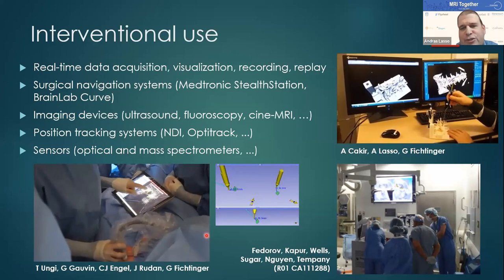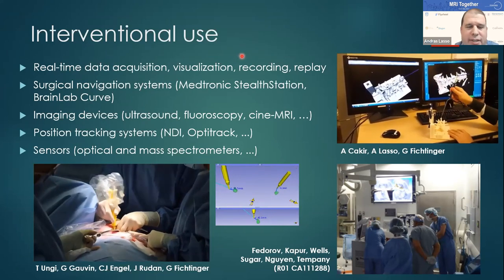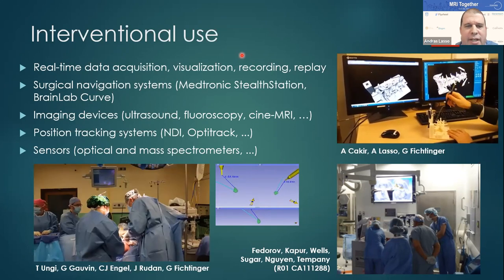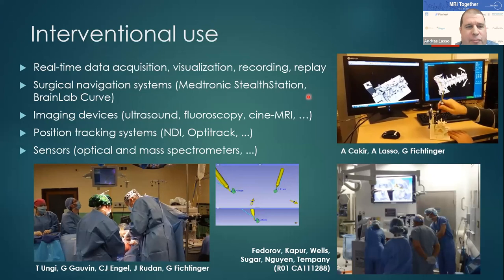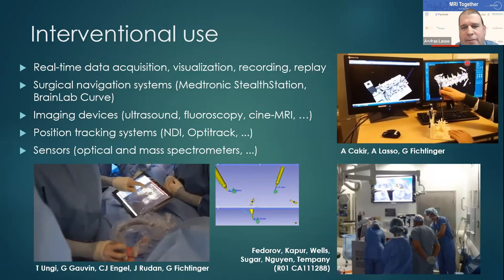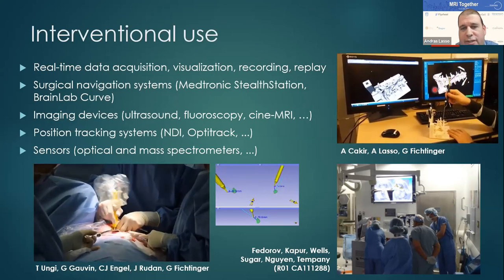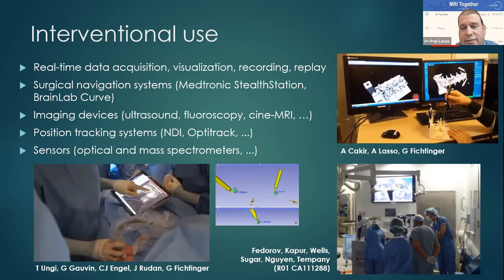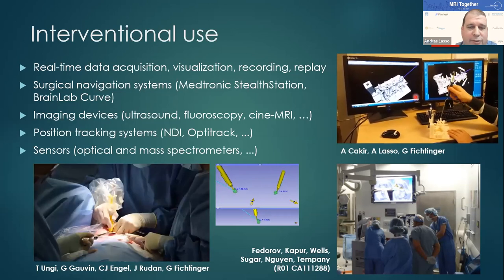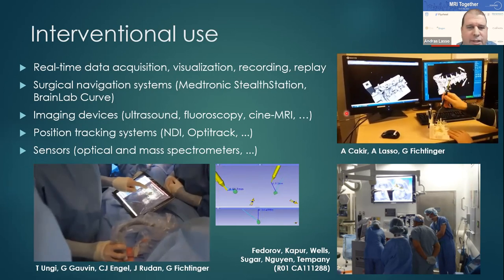Slicer can also be used for interventional guidance. It can acquire data from a wide range of sources including images, navigation systems, and various sensors, and record, visualize, and replay data. For example, you can connect to commercial surgical navigation systems — this shows a Medtronic navigation station screen mirrored in Slicer — which is useful because you can add your own custom additions to the Slicer navigation screen without interfering with the commercial system. This is robust enough to be used for actual interventions.